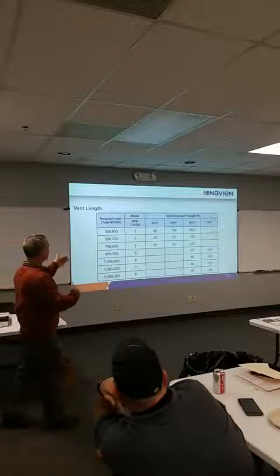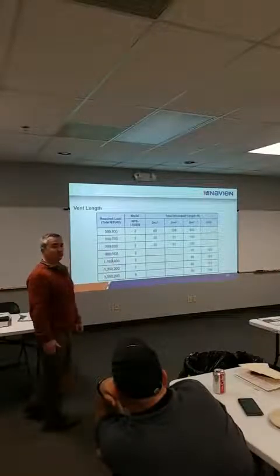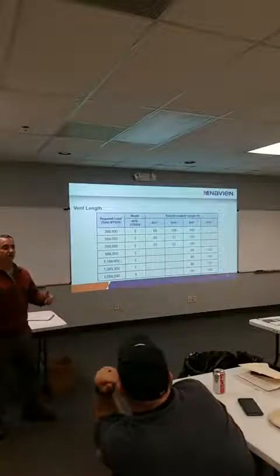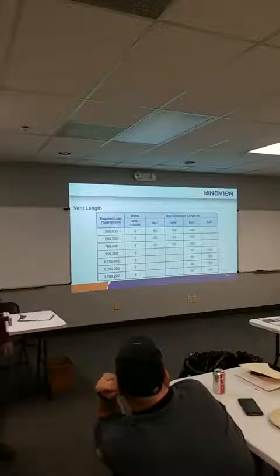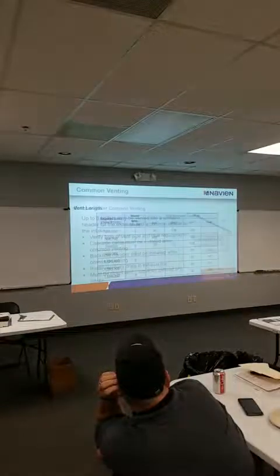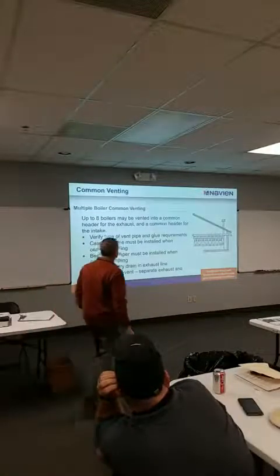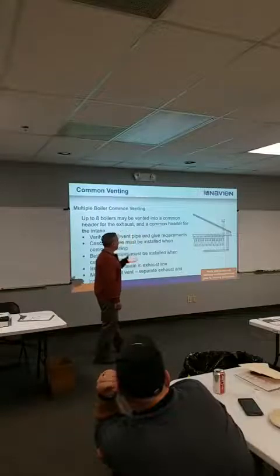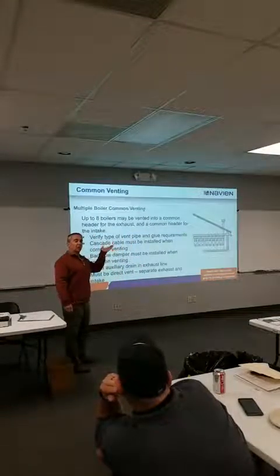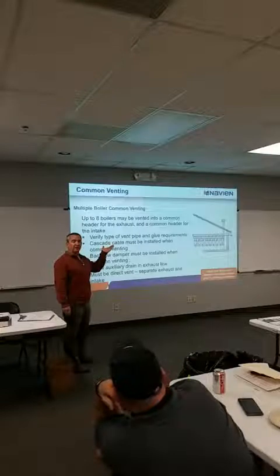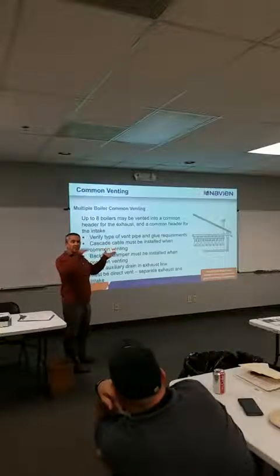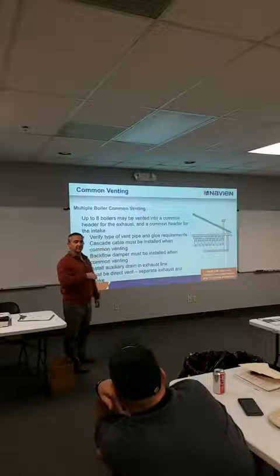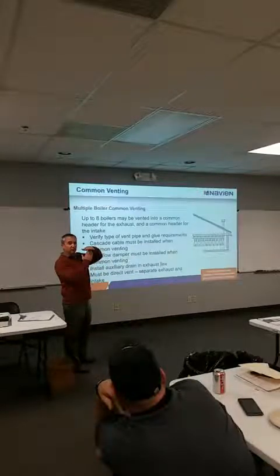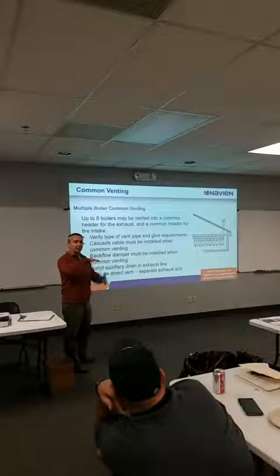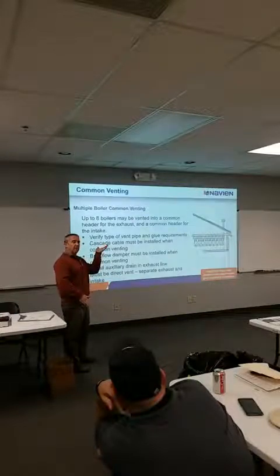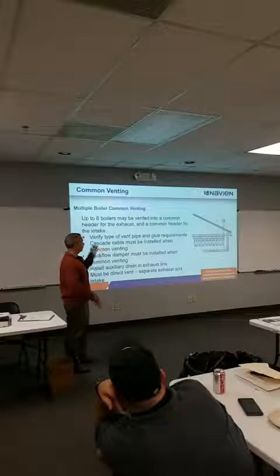So you've got 2 units, 60 equivalent feet using 3-inch pipe. They come off with 2-inch. We recommend, and I don't know if I got a good picture of this, this is an okay picture. Usually we want to come off on the vent and put an elbow back into your manifold pipe. That way any condensate that collects in that manifold pipe has a pathway to your condensate T. If you tee into the bottom of that manifold pipe, any condensate could actually drip down onto that flapper assembly. So elbow up and then back into your condensate T.